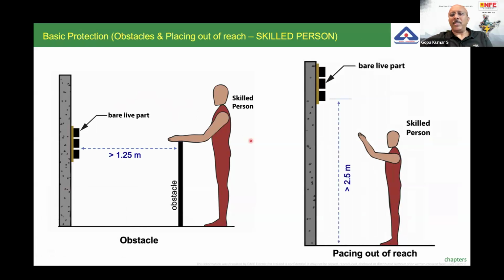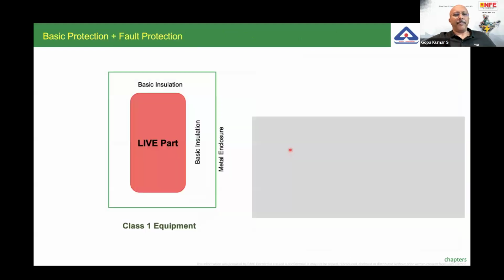Similarly, placing out of reach. Placing out of reach in public places, of course, the distances are more, whereas in places where skilled people are working, then the placing out of reach is different. Example, you have the live conductor. There is a person, it should be at least 2.5 meters away, 2.5 meters height, so that accidentally nobody touches. So these are also recognized as obstacles, and placing out of reach is also recognized as a basic protective measure, but this is applicable for a location where skilled people work.